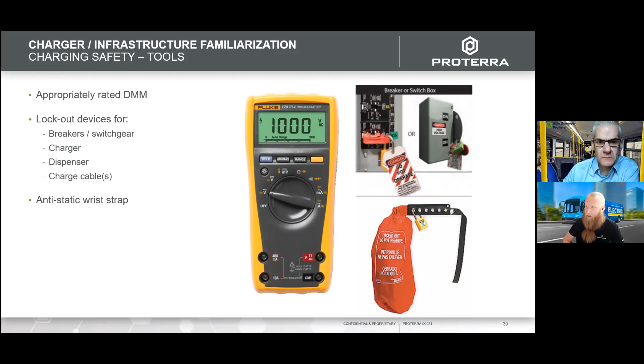To start out, make sure that you disconnect the input, the AC side of things, and lock it out. The switchgear itself or the circuit breaker needs to be shut off and locked out. Apply a lock and tag explaining who is working on it and what's being done. Disconnect the load or the vehicle from the charger. Again, we want to make sure that the ESS does not backfeed into the charging system as you're working inside of the charger.